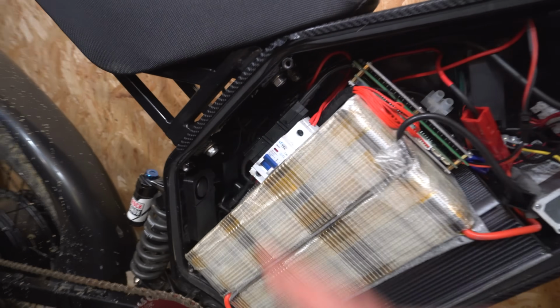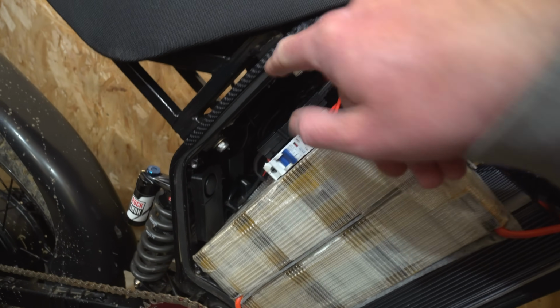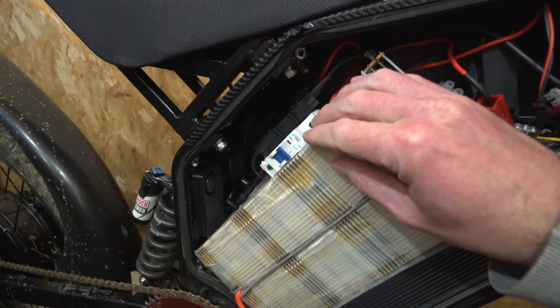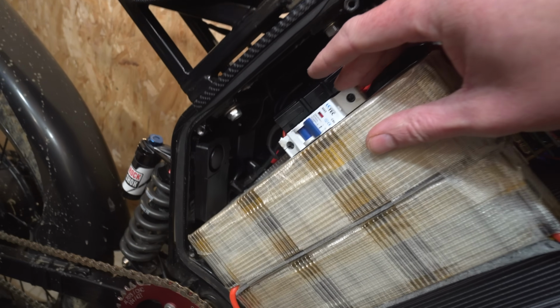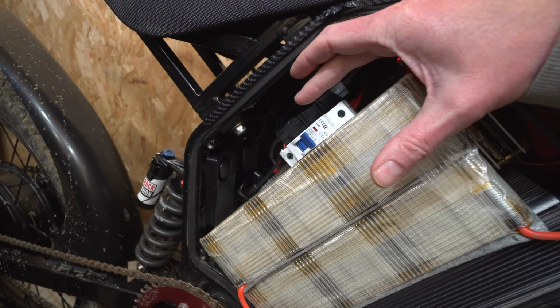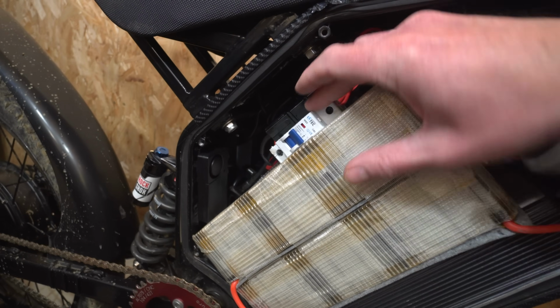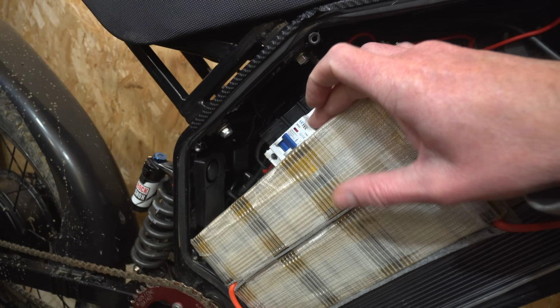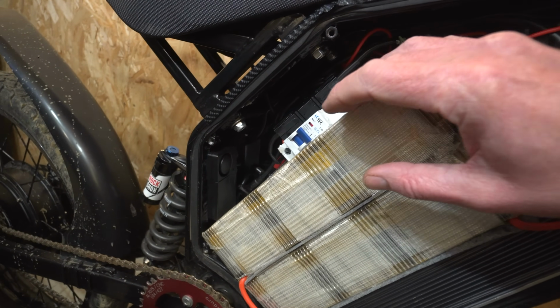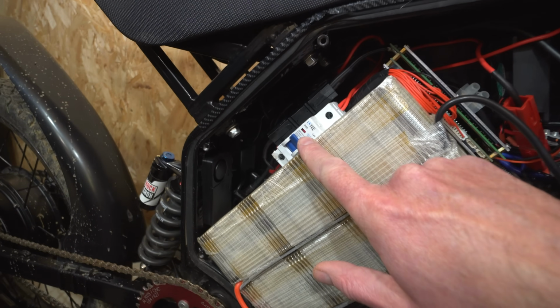The master breaker is on the side here. It was mounted elsewhere, but I've just stuck it onto the side of the battery now. This is basically just an AC breaker, and you can parallel these up to get more power. I find around 8 kilowatts this is fine, but if you really gun it for a continuous amount of time, it will trip, and that's when you can put multiple breakers in.